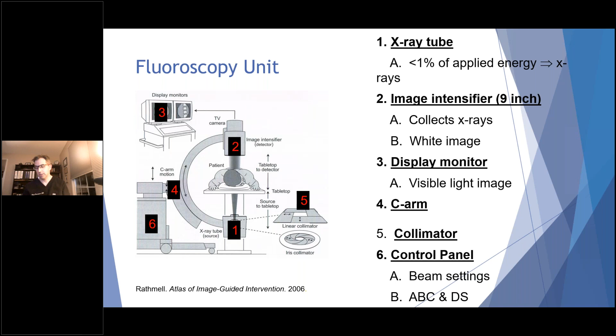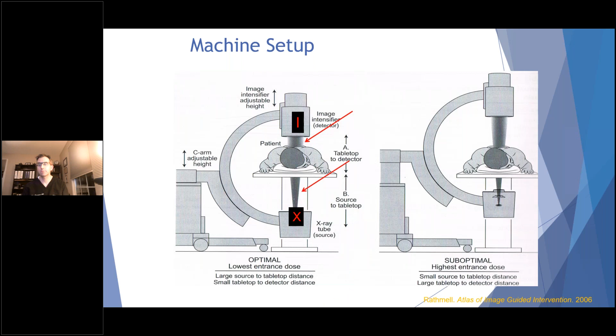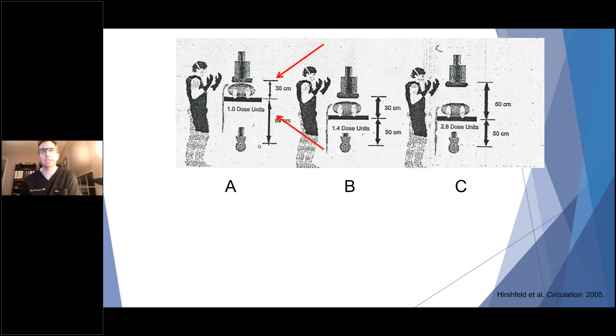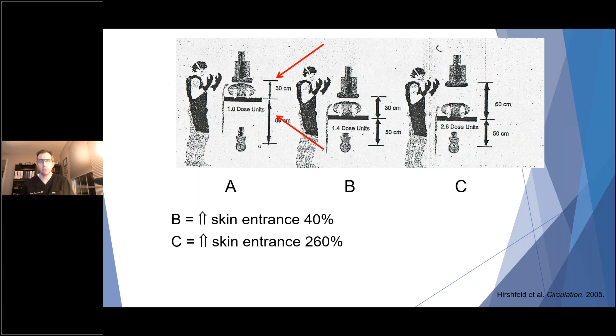When you use the machine, as was discussed, the image intensifier should be as close to the patient as possible. The X-ray tube should be as far away as possible. This is optimal. These small steps substantially lower your exposure. Look at this, for example. Here, when you look at the figure on the left, the II is very close. The X-ray tube is far away. Now look at this, C. The II is far away. The X-ray tube is very close. That's not optimal. Look at the difference in exposure. The difference between A and C, the skin entrance exposure is over 260% higher. By just making small changes, you lower the exposure substantially.